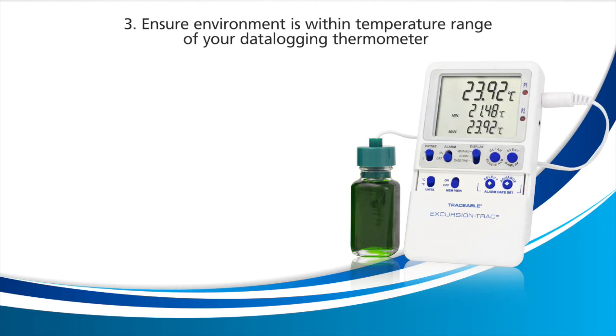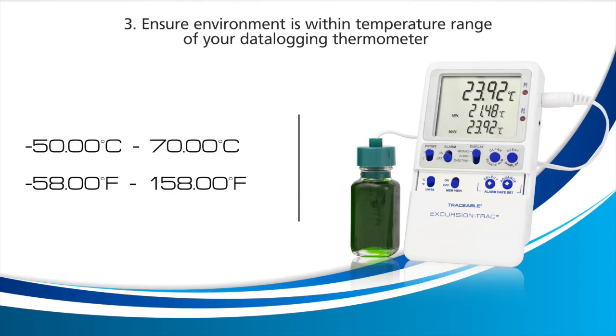The third remedy is to ensure you have your probe in an environment inside the temperature range of your data logging thermometer. For this data logging thermometer, the temperature range is -50 to 70 degrees Celsius and -58 to 158 degrees Fahrenheit. If your probe is detecting a temperature above or below these temperature ranges, your device will display an LLLLL as it isn't capable of reading above or below these temperature ranges. Ensure that the temperature environment is in between these temperature ranges and see if the error goes away.